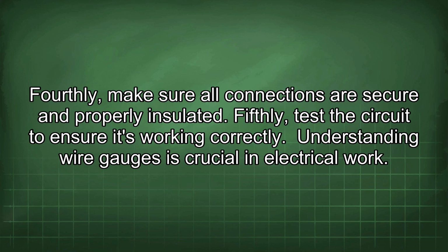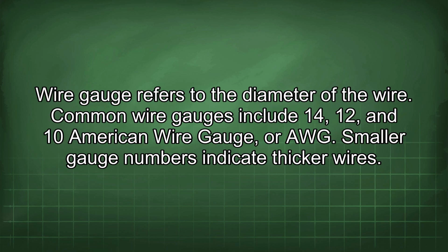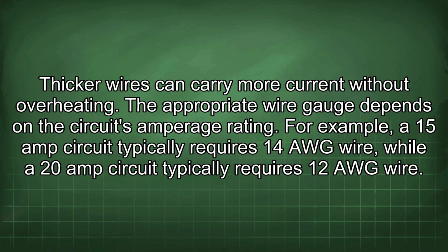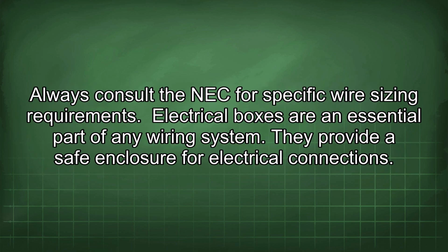Understanding wire gauges is crucial in electrical work. Wire gauge refers to the diameter of the wire. Common wire gauges include 14, 12, and 10 American wire gauge, or AWG. Smaller gauge numbers indicate thicker wires. Thicker wires can carry more current without overheating. The appropriate wire gauge depends on the circuit's amperage rating. For example, a 15 amp circuit typically requires 14 AWG wire, while a 20 amp circuit typically requires 12 AWG wire. Always consult the NEC for specific wire sizing requirements.